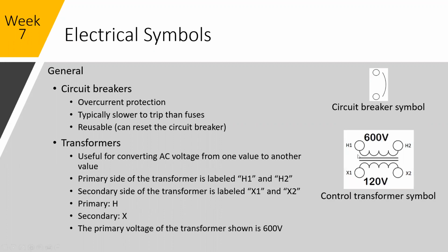So transformers, these are used for converting AC voltages. This is typically what they're going to look like. You have here a primary side, H1 and H2, and your secondary side, X1 and X2. These could also be primary voltage or high side, low side. This one, almost always, there's going to be notes beside it detailing your incoming voltage, your outgoing voltage. The transformer might have information on whether it's oil cooled, air cooled, the type of oil, whether or not the windings, there's different windings for different voltages. But they'll all typically look like this and maybe have additional grounding beside it.